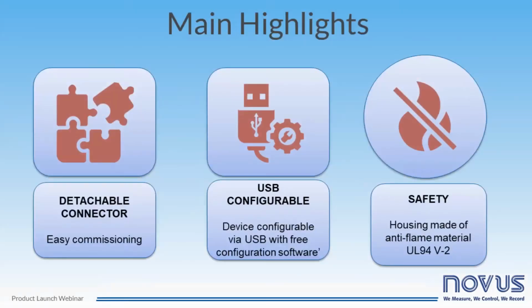One key advantage of the N1050 is its detachable connector, which makes installation, commissioning, and maintenance a very easy task. By the way, this feature is a global exclusive of the latest launch of the Novus PID controller. No other competitor has a detachable connector. The device setup can easily be made through its keyboard, navigating the menu and setting the parameters. Its USB port is an additional value, allowing a more convenient way of configuring the N1050. Machine manufacturers, for example, can reduce setup time by configuring devices in batch using the configuration software.